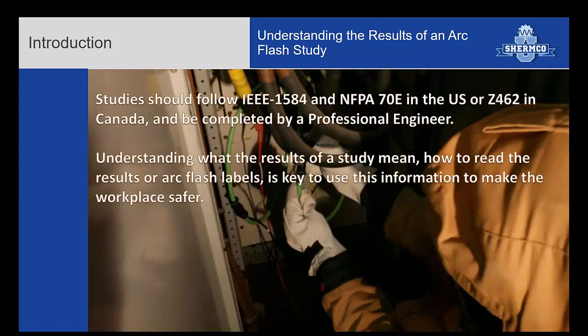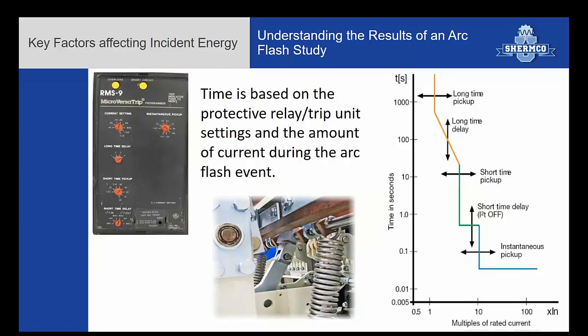And then there is understanding what those results mean, and that's what we're going to talk about a lot today: how to reduce incident energy. Just understanding what the results of a study mean really is important to the worker so that they can understand how to be safe. So first I was going to talk about some key factors that affect incident energy. One of the biggest being time. So once an event happens and a worker's exposed to an arc, how long they're exposed is a big factor in how much incident energy they're actually seeing or being exposed to. And those times can be like 0.05 seconds to 0.3 seconds.